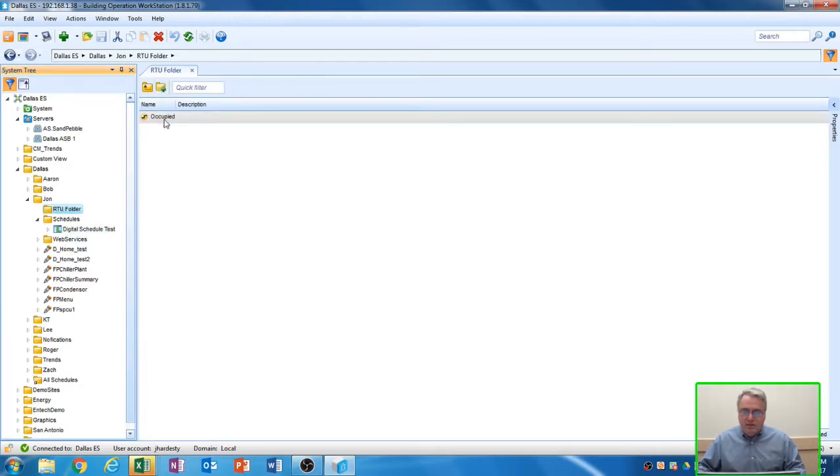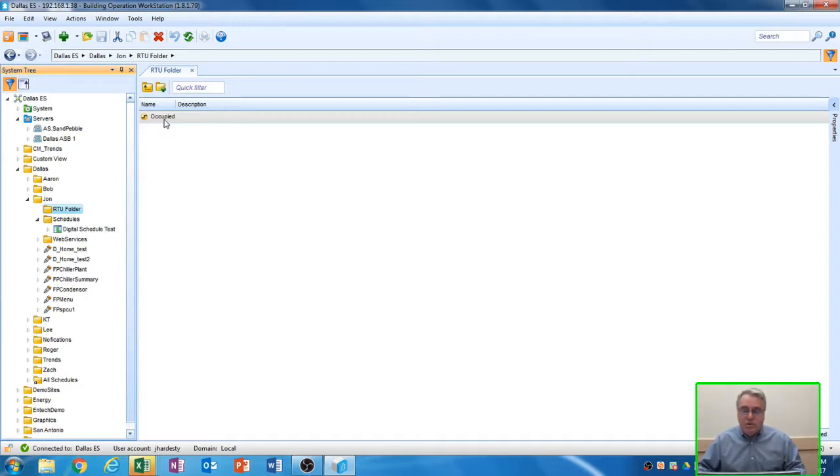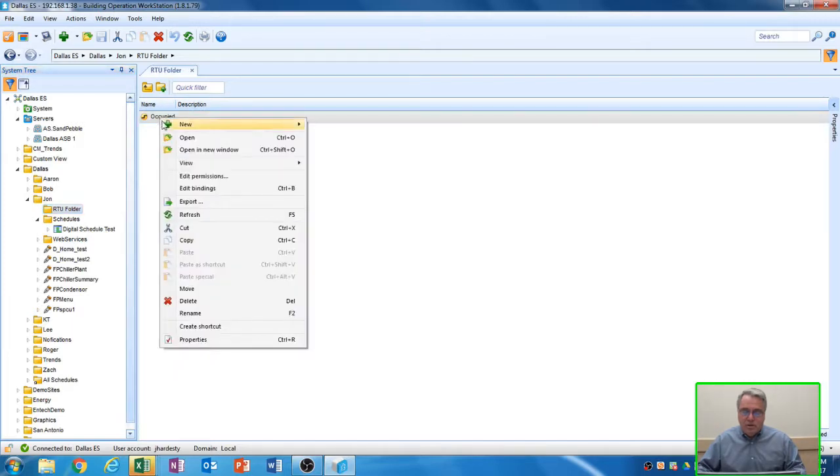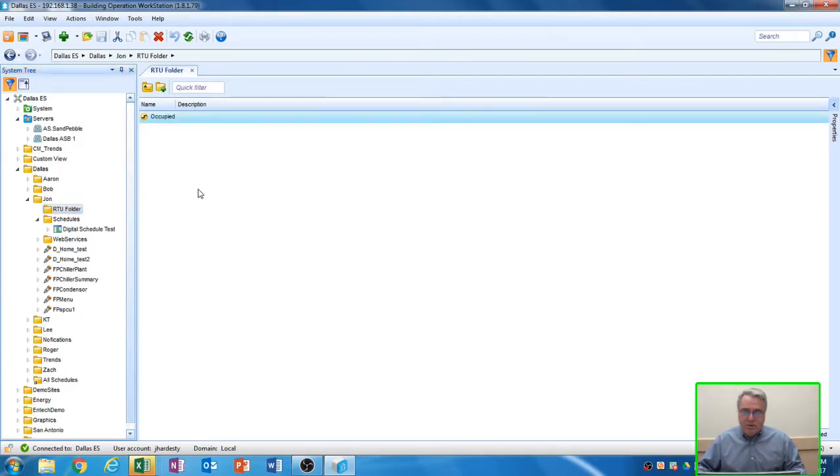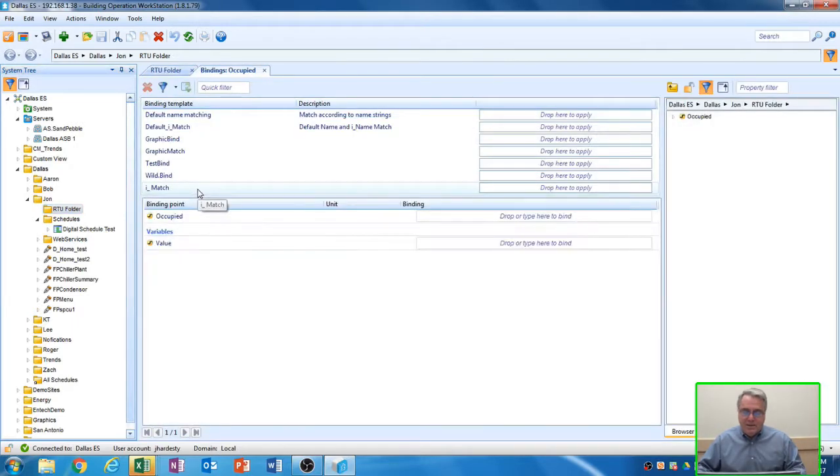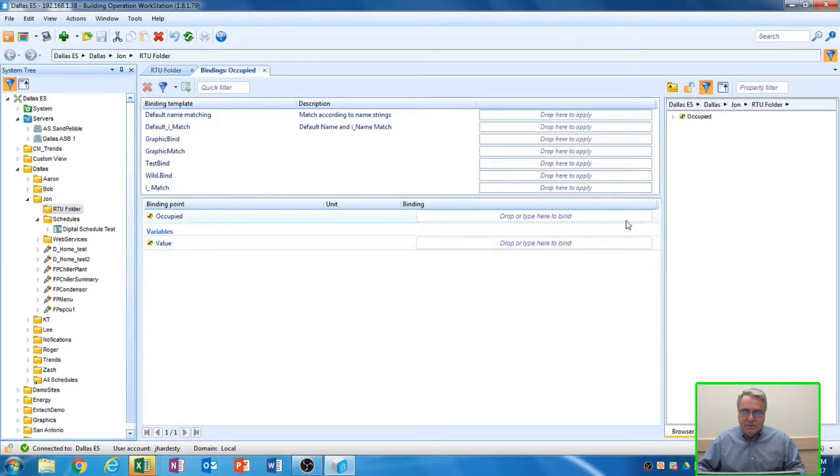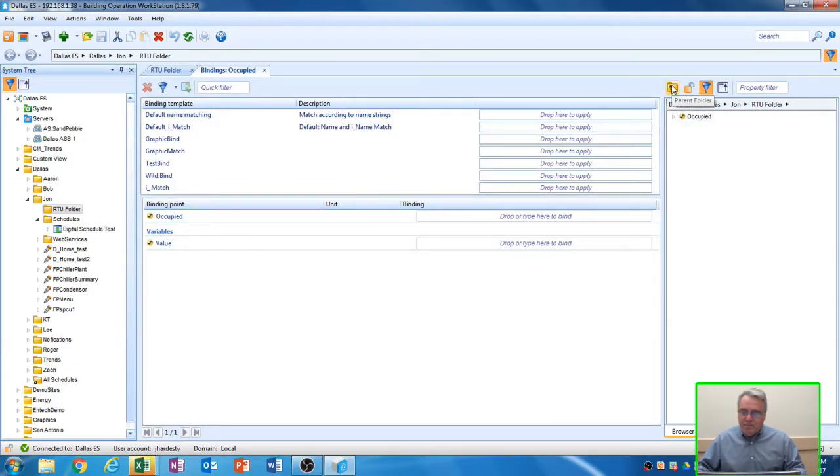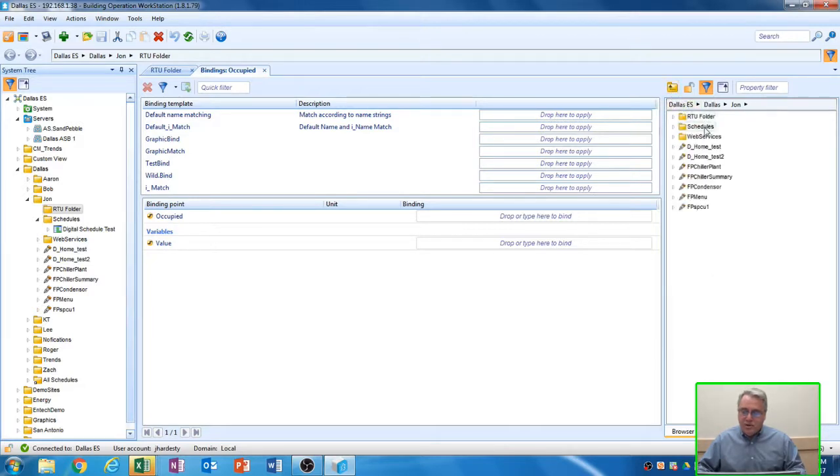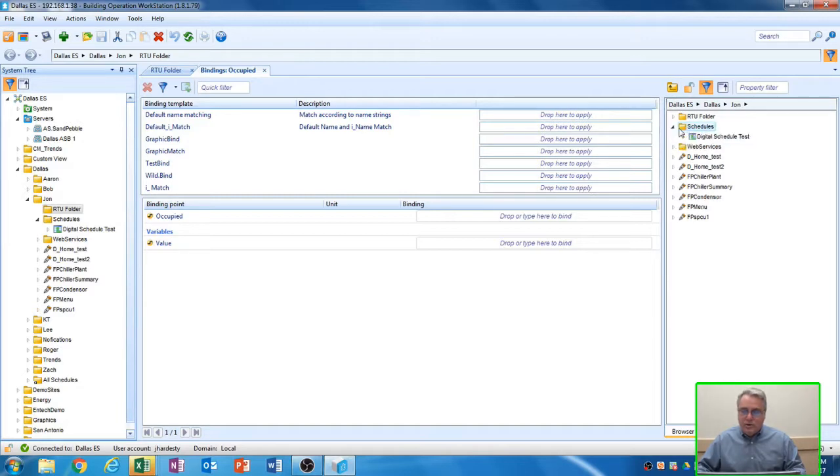I've created a folder called rooftop unit folder. In there, I have an occupied software point that I'm going to attach this schedule to. The way that you have this schedule control this point is you right-click on it, go to Edit Bindings, and then over here on the right-hand side, we'll want to go back on the object tree until we see our folder called Schedules. Select the folder we created called Schedules, and under that folder, you'll see that new schedule that I created.